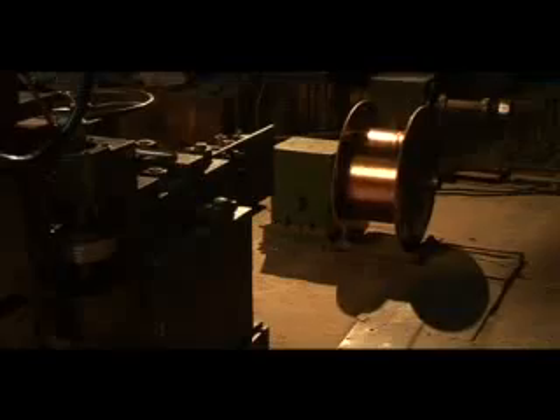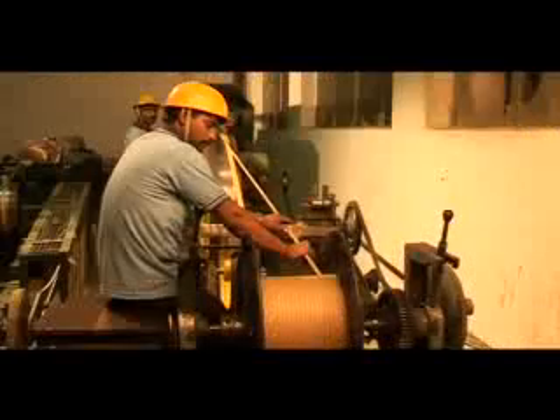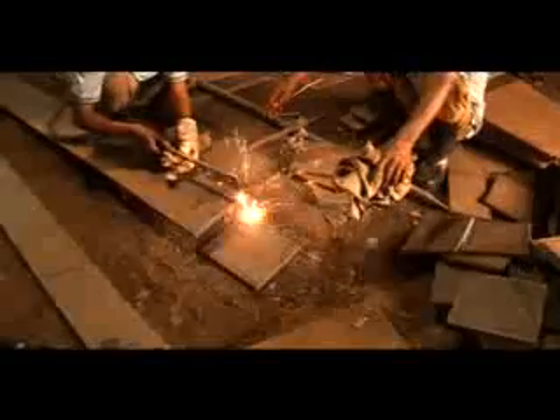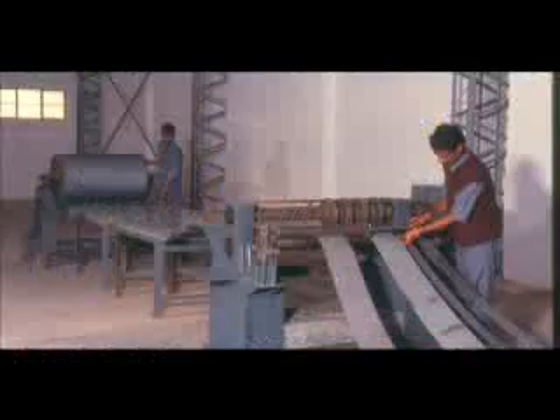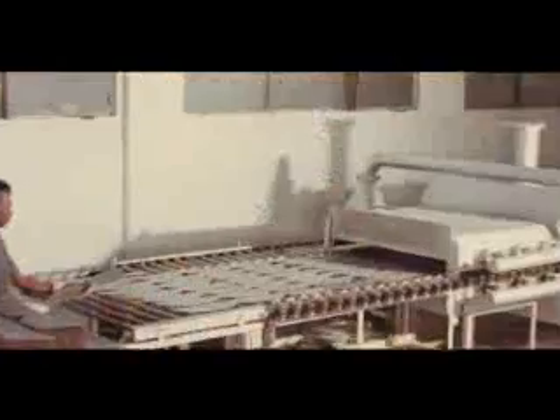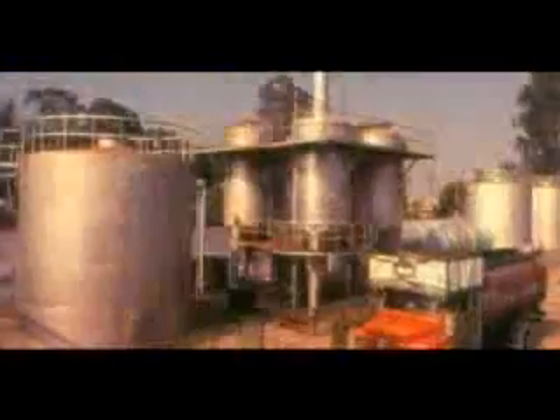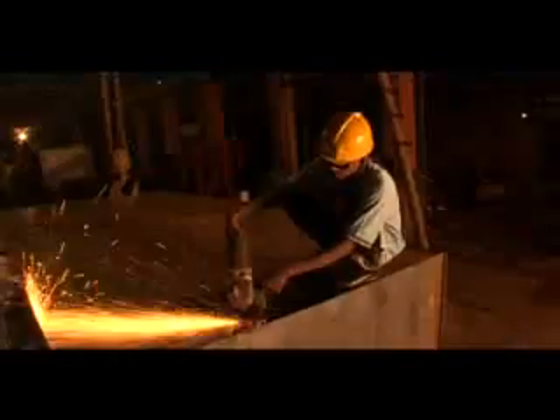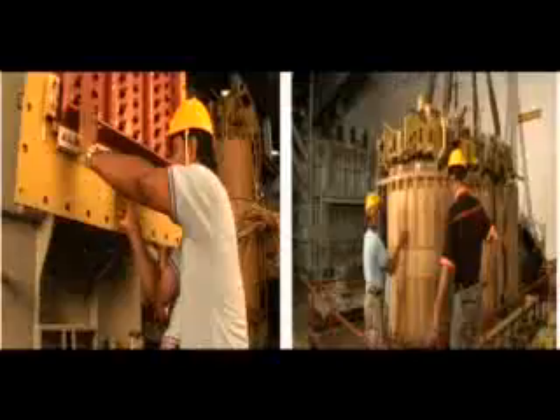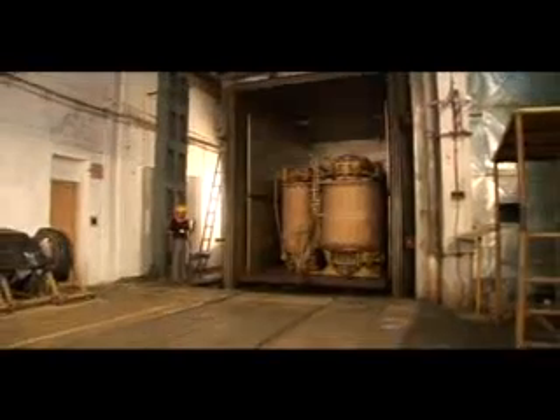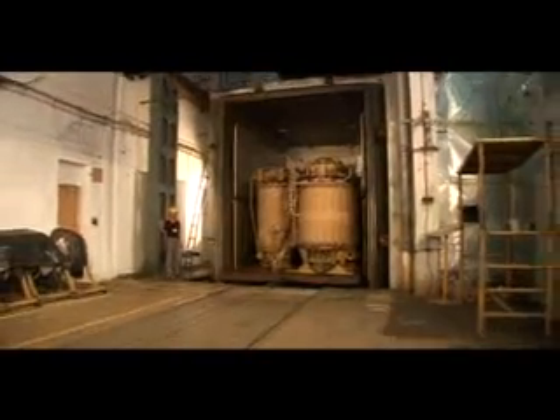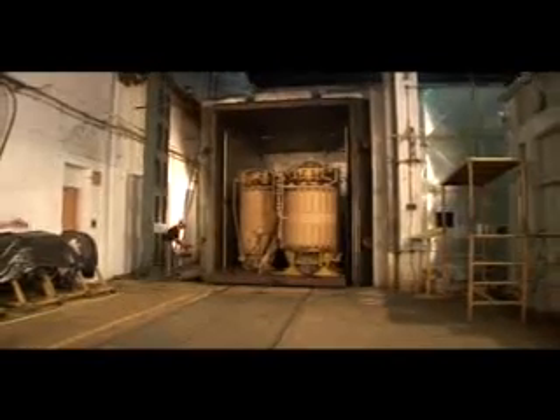Unlike most transformer manufacturers, Technical Associates Limited has invested heavily in backward integration and does in-house production of major raw materials. Separate shops have been provided for core processing that includes slitting, cutting and annealing, conductor manufacturing including drawing, annealing and paper covering, transformer oil filtration and processing, tank fabrication, winding, assembly and tanking. An autoclave with vacuum capacity up to 1 torr is used for drying the transformer, and a vapor phase drying plant is expected to be installed shortly.